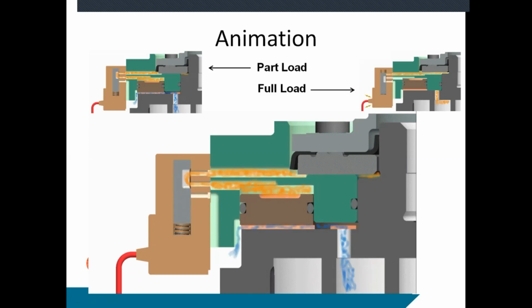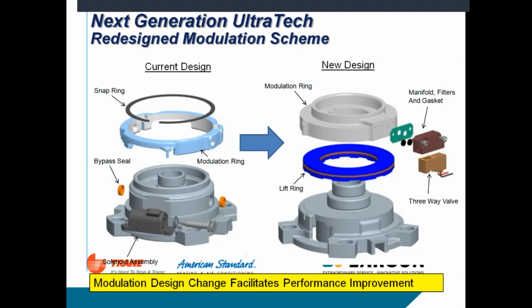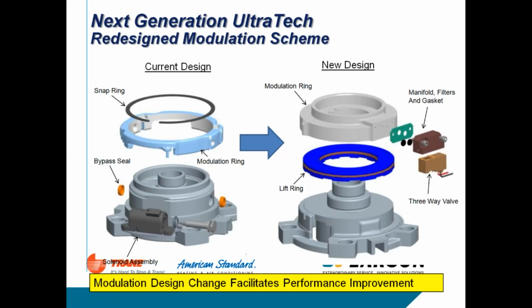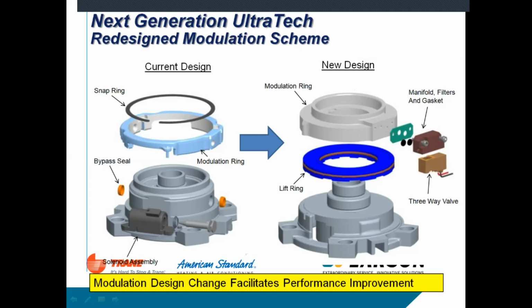It will change the efficiency, or I guess longevity. The solenoid is kind of the weak spot. This three-way valve is probably going to be a lot more reliable. Basically, it does the same thing. Here's the old system with the solenoid valve, and it just moved the scroll plate a little bit. The new system changes the direction of gas in through this portion of the scroll here.